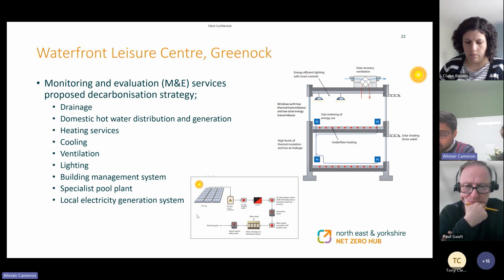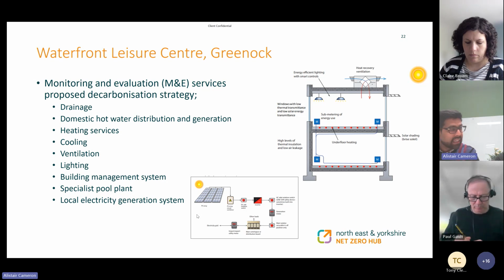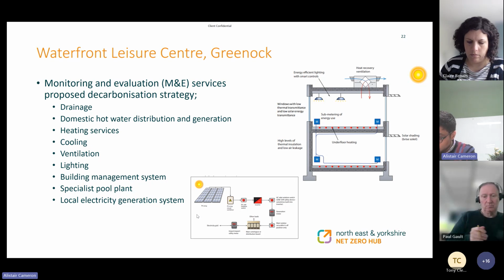So very briefly, if we did have ground source heat pumps, we felt without any significant fabric upgrade, we would probably need about 70 boreholes, and each borehole would have to be 7 metre spaced and go down around 180 metres based on the geographical conditions of the ground at Inverclyde.